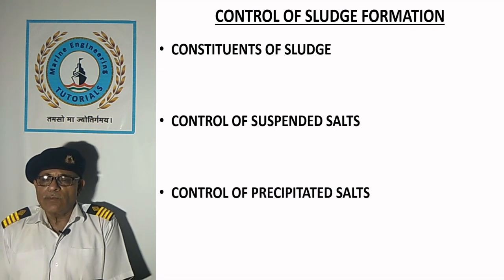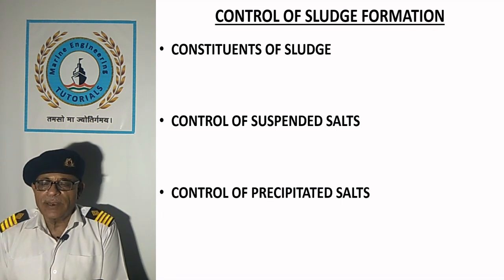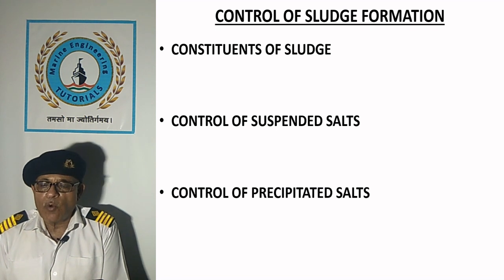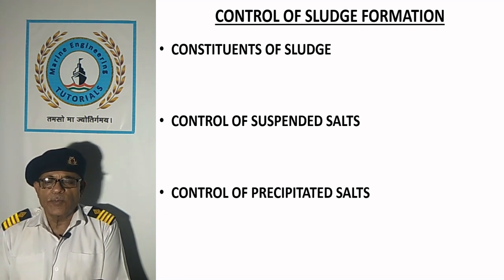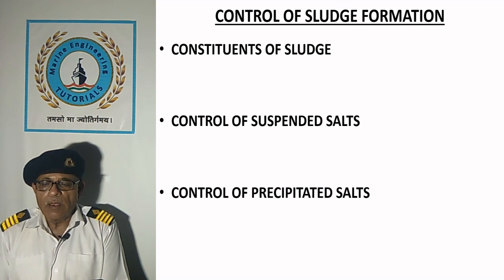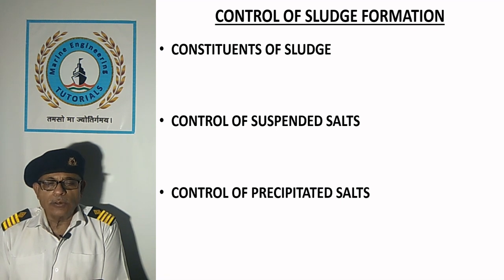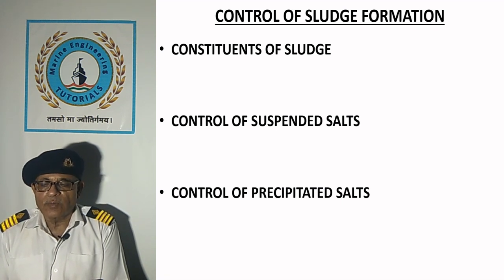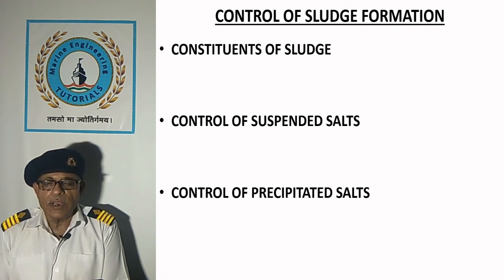Control of precipitated salts: calcium carbonate, magnesium hydroxide and calcium sulphate are not soluble in boiler water and tend to deposit scale. Calcium and magnesium phosphates produced by chemical reactions are precipitated. All these salts must be removed from the boiler by periodic blowdown to prevent their accumulation and subsequent deposition.